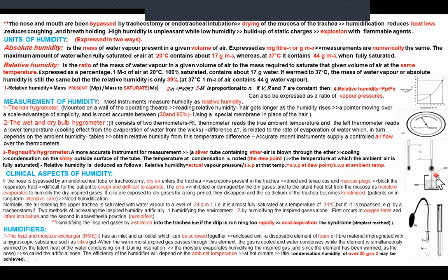So that definitely this thermometer will be exposed to a lower temperature because of the latent heat of vaporization. Of course, we ought to have a proper current in the vicinity of this area to assure the process of evaporation. The difference between the two thermometers will be taken from tables where we can measure the relative humidity. Nowadays, of course, new instruments are capable of inducing air circulation around this area automatically.